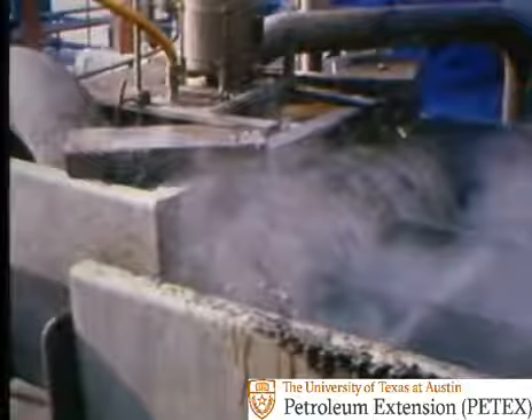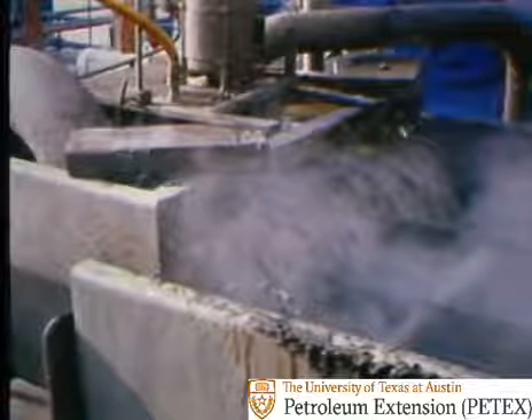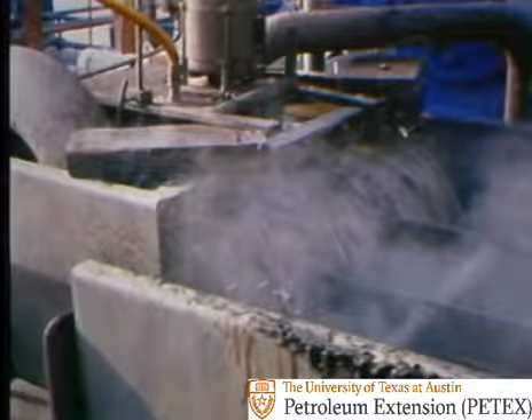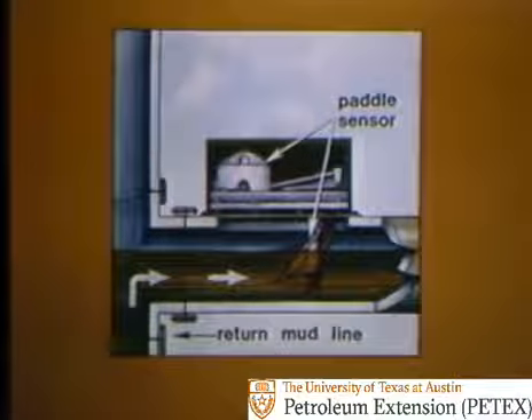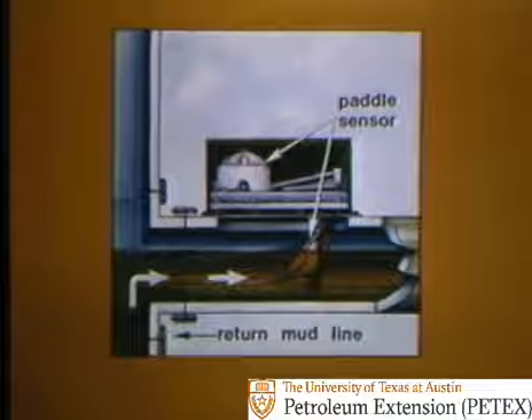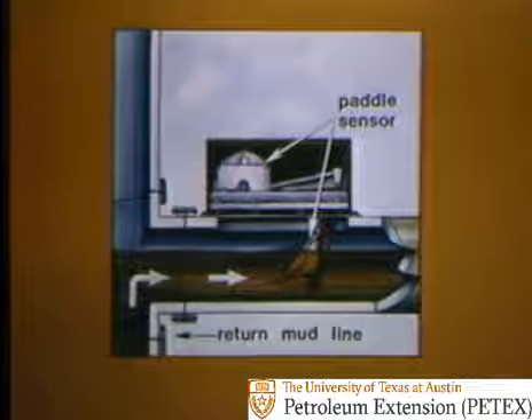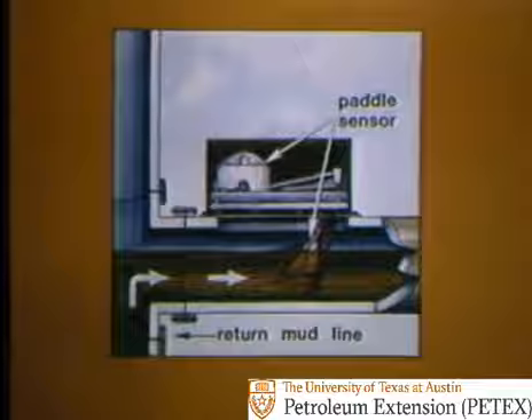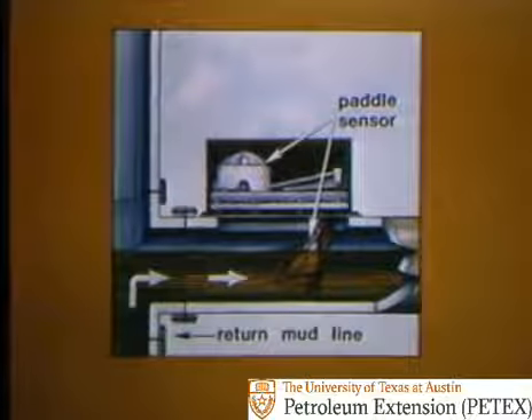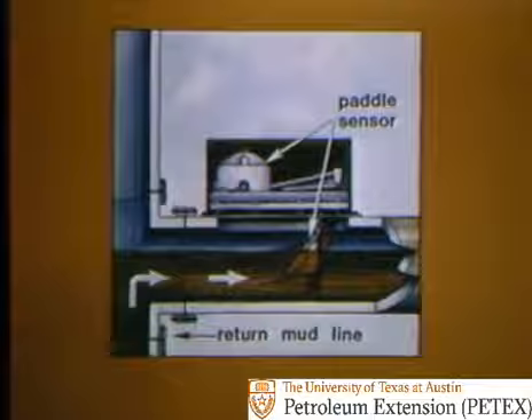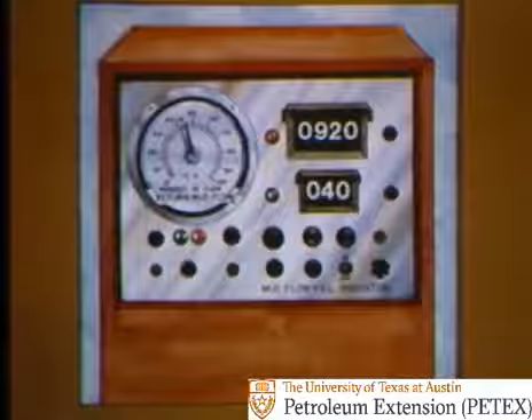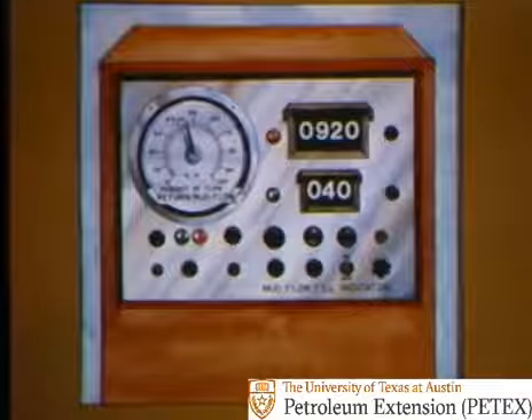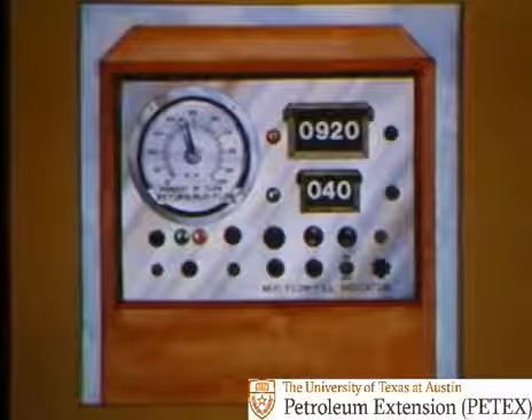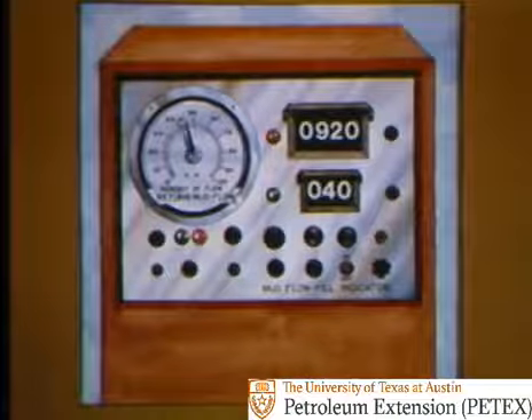First, let's say you're on bottom drilling. One sign of a kick is an increase in the return rate of the mud coming back over the shaker. So, a return flow sensor can help. It has a paddle in the return line that's moved by mud flowing past it. The moving paddle sends a signal to a meter on the floor. It warns you if return flow increases.